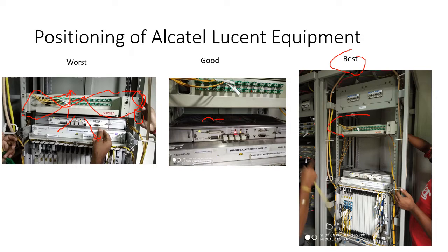This fiber termination unit has been repositioned to the maximum on the top side. So now this vacant space is available, and from that the air ideally goes on the top side, and it is overall improving the cooling efficiency. Before, the air was coming out from this fan and instead of going upside it was coming like this. It was also going on this equipment.